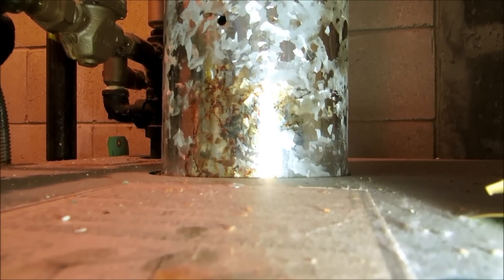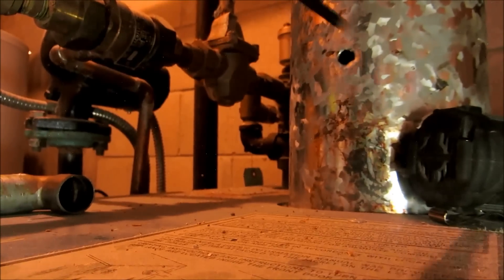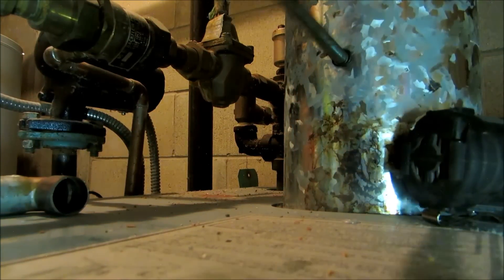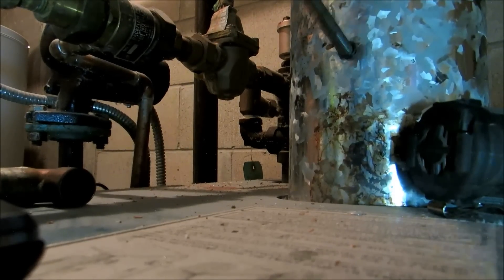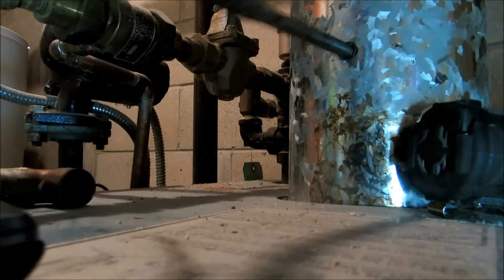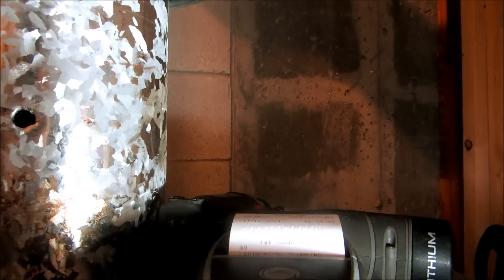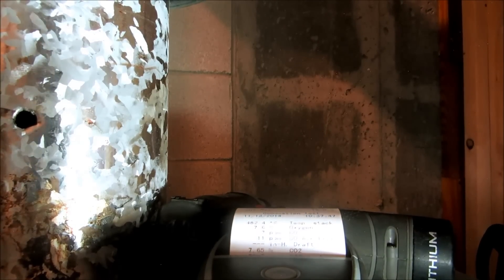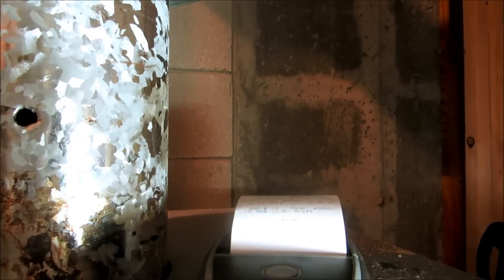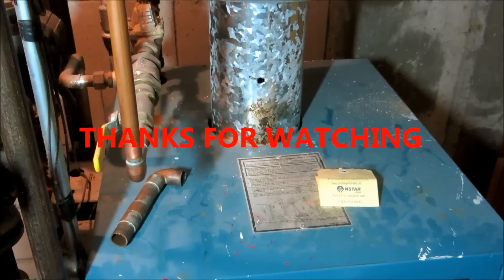I want to do a smoke test in there. We'll check that. No smoke. Alright I got that all done. Gas valve set, combustion analysis done. Good to go.